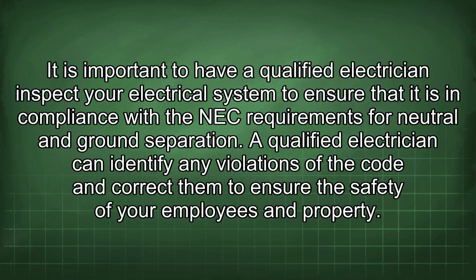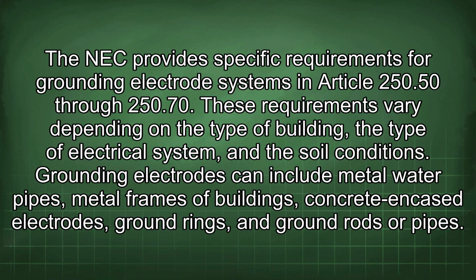It is important to have a qualified electrician inspect your electrical system to ensure that it is in compliance with the NEC requirements for neutral and ground separation. A qualified electrician can identify any violations of the code and correct them to ensure the safety of your employees and property. The NEC provides specific requirements for grounding electrode systems in Article 250.50 through 250.70.